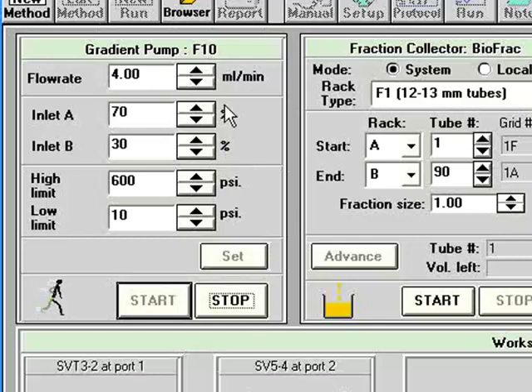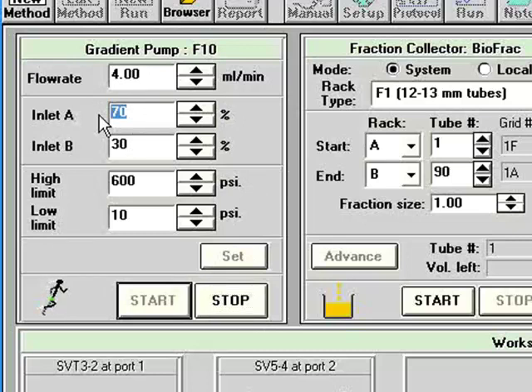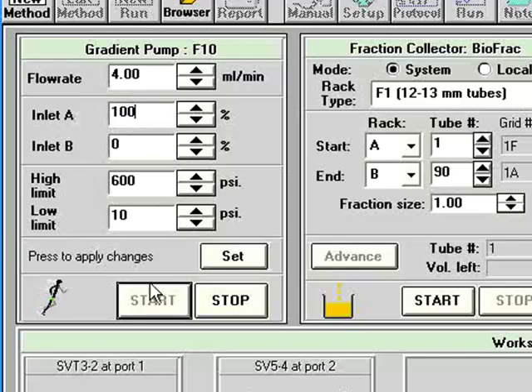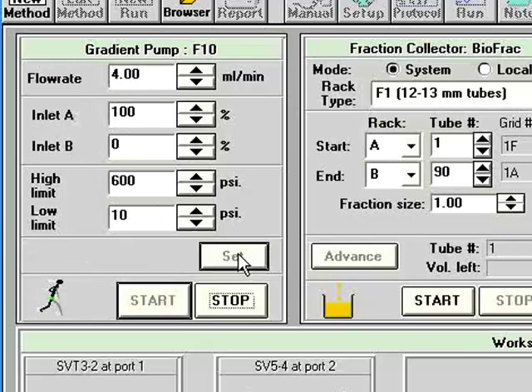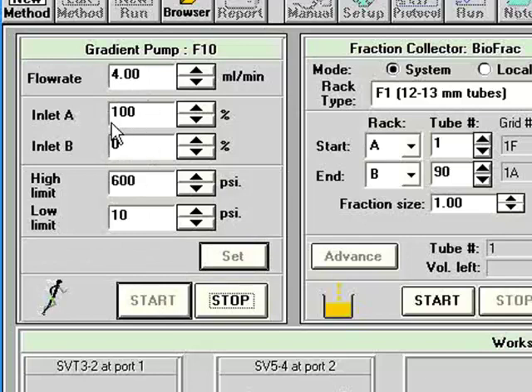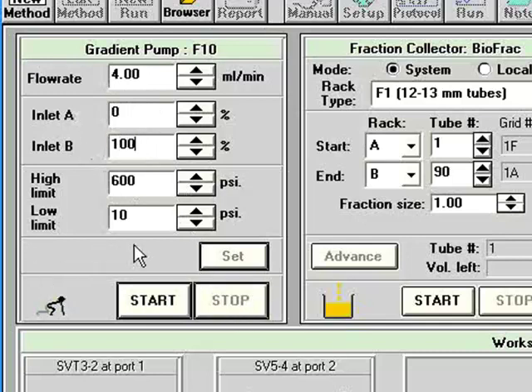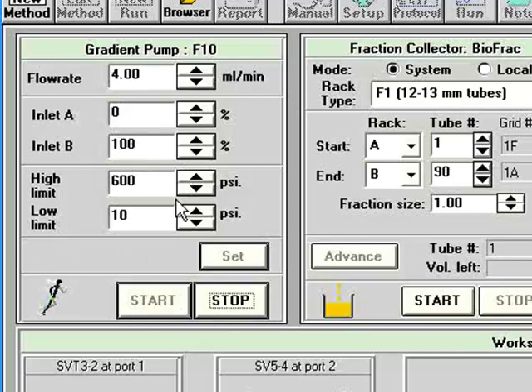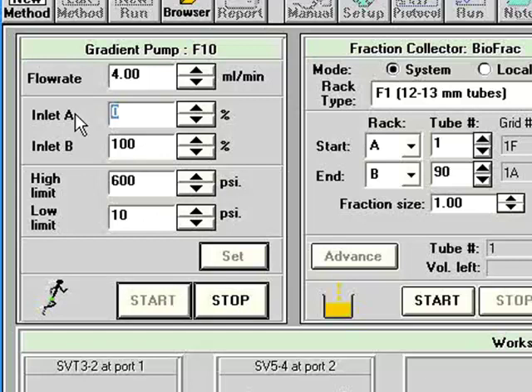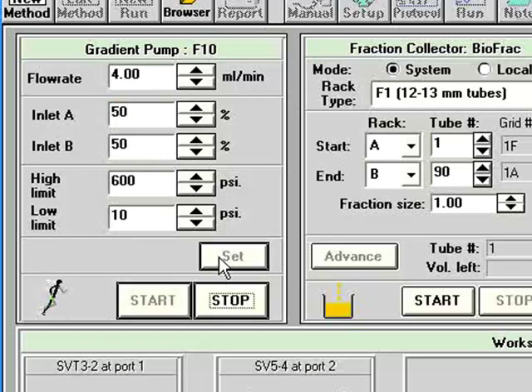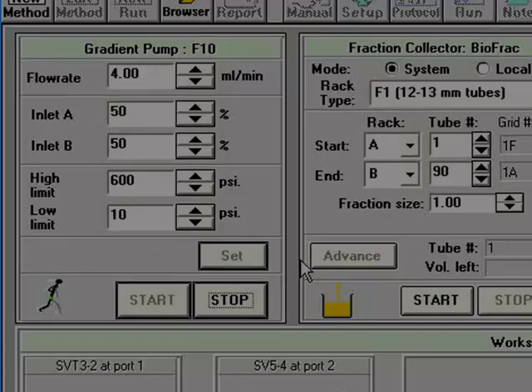So we can purge the system. If you decide that you want to pump, let's say, 100% of A through the system, while it's running, you need to click set, and then it will go to 100% of A. Same thing if you're running on the fly and you want to change these percentages. Otherwise, you can click start, then go to, let's say, 100% of B, and then click start, and it will now be at 100% of B. So it depends. If you're running on the fly, you can change things while it's running, but you have to click set to make sure it's changed.